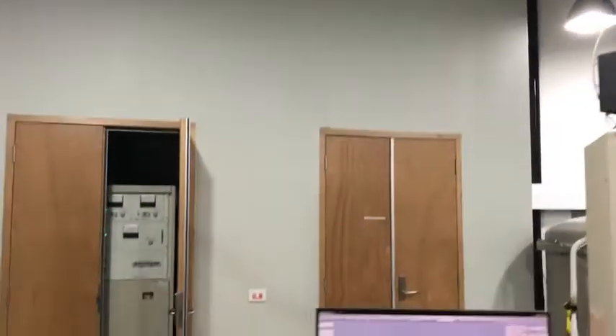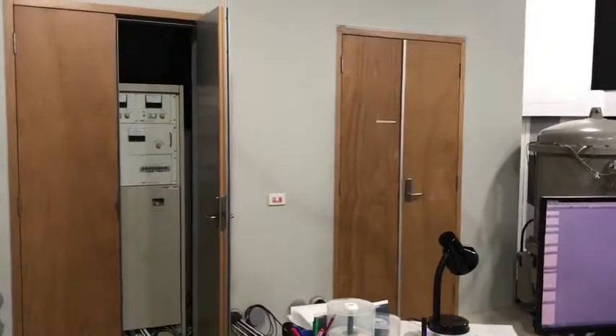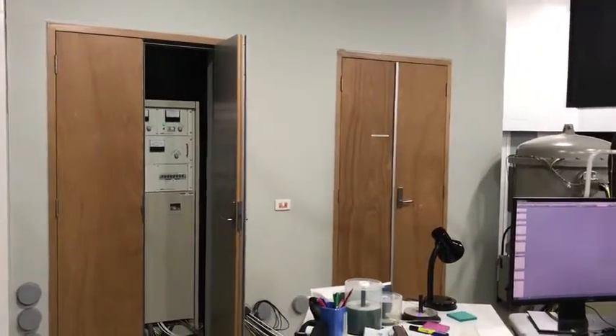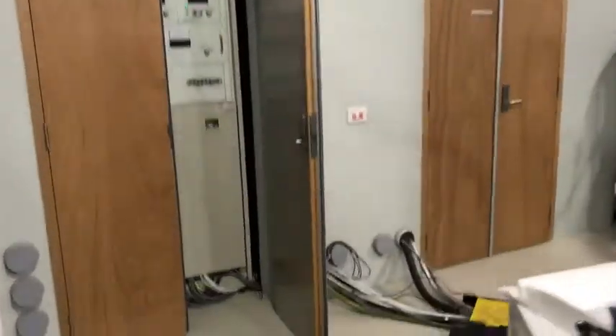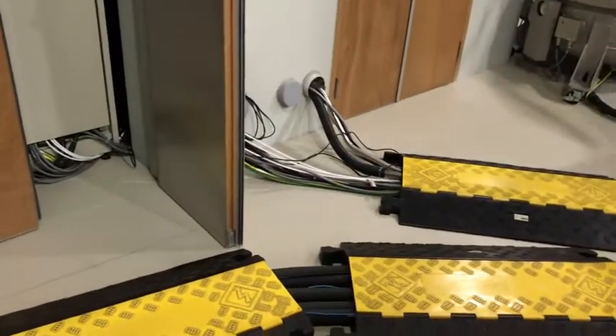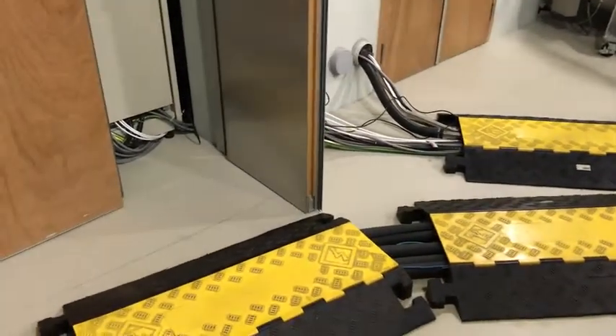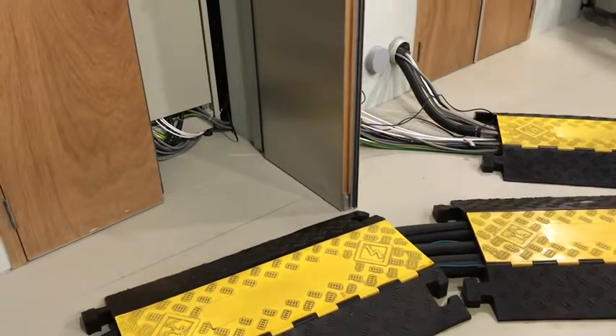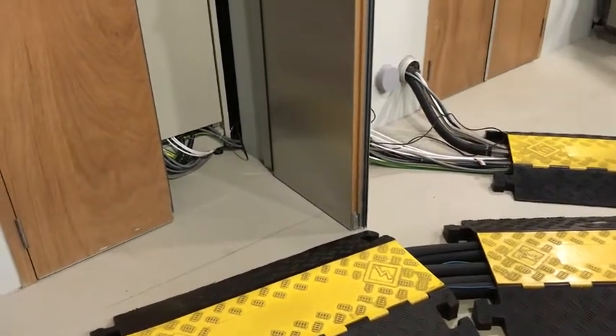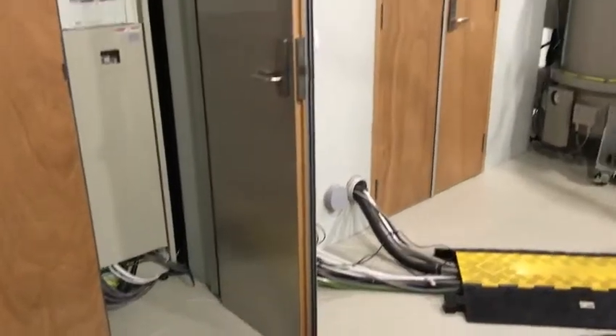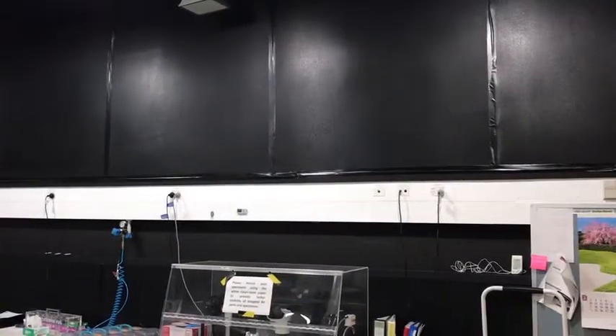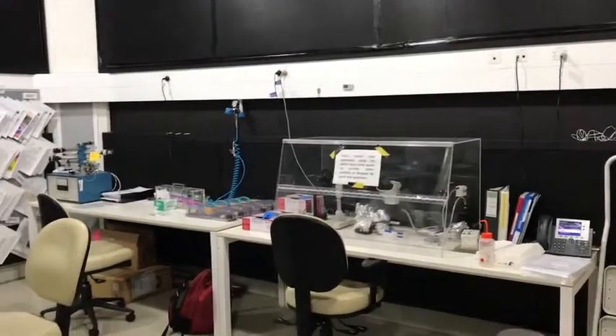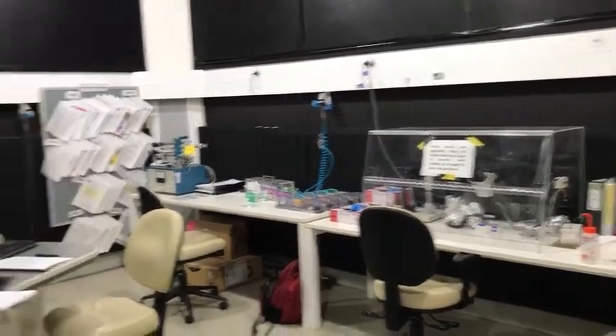Now the wall of that service hutch is not coated in foam, but that's because if you look at the floor, you can see the seam in the foundation there, and we'll get onto the foundations in a second. That does not look parallel to the walls of the hutch, and that's because the wall of the hutch was designed to not be parallel with the opposite wall, so that you can't set up resonance. Okay, there's a specimen preparation bench right there. We'll use that in a second.